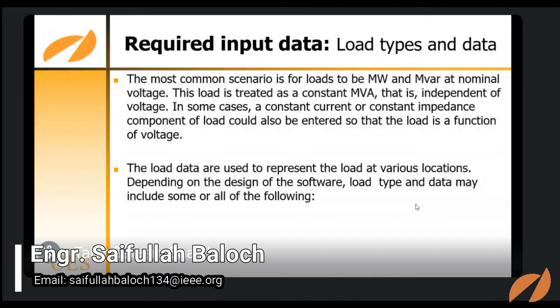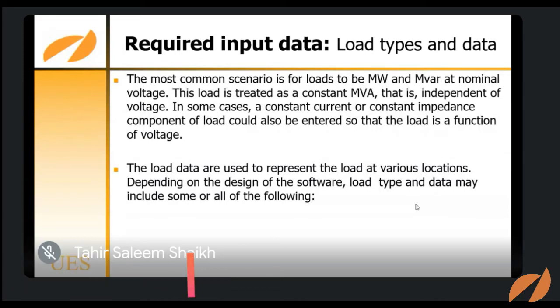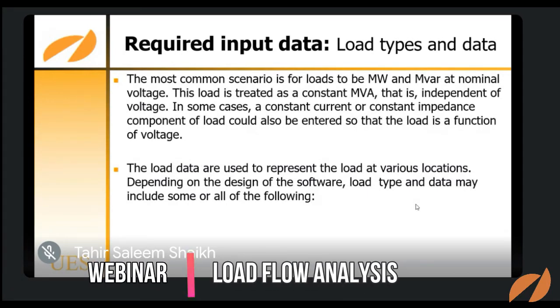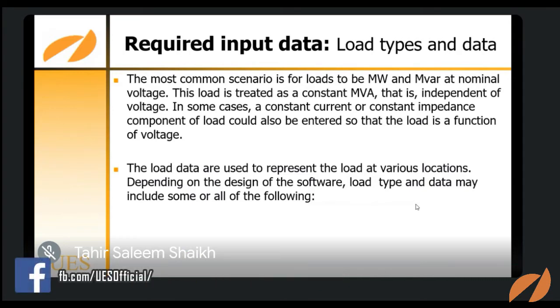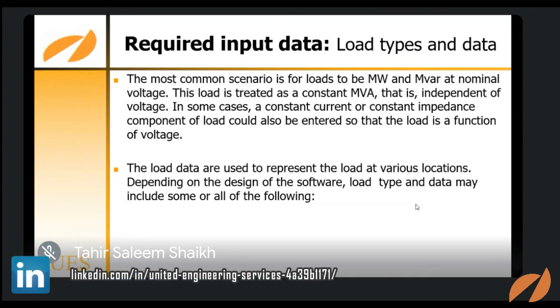Okay, so the most common scenario is for loads to be entered as megawatt and MVAR reactive at nominal voltage. This load is treated as a constant MVA load that is independent of the voltage. In some cases, a constant current or constant impedance component of load could be entered, so the load is a function of voltage. The load data are used to represent the load at various locations depending on the design of the software. Load type or data include some or all of the following.